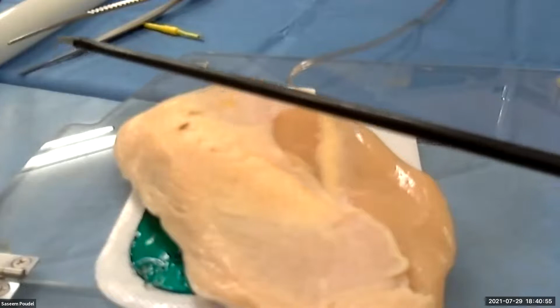So how do you check? I have with me here one type of insulation tester. It's a very small device. If you just go here, to the tip, and I just need to put it here. When there is insulation failure, it gives a sound. It's a very old instrument. And when there is no insulation failure, at the normal part, it does not make any sound.